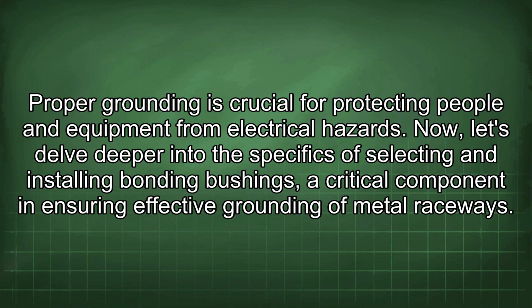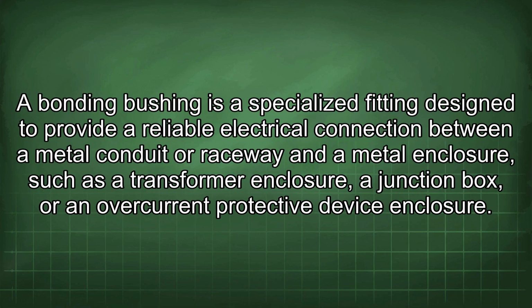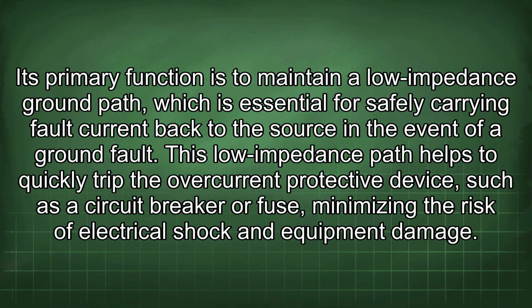of metal raceways. A bonding bushing is a specialized fitting designed to provide a reliable electrical connection between a metal conduit or raceway and a metal enclosure, such as a transformer enclosure, a junction box, or an overcurrent protective device enclosure. Its primary function is to maintain a low impedance ground path, which is essential for safely carrying fault current back to the source in the event of a ground fault. This low impedance path helps to quickly trip the overcurrent protective device, such as a circuit breaker or fuse, minimizing the risk of electrical shock and equipment damage.